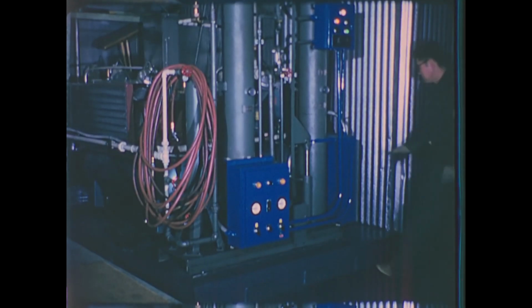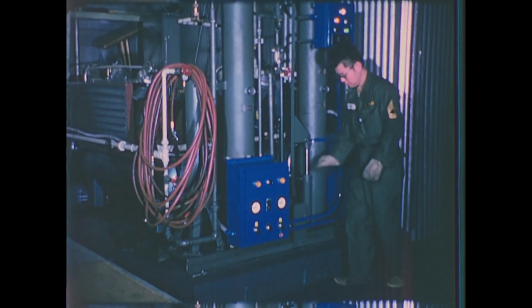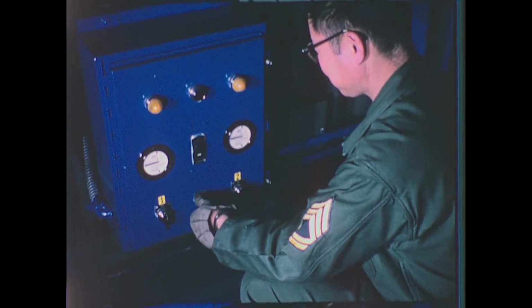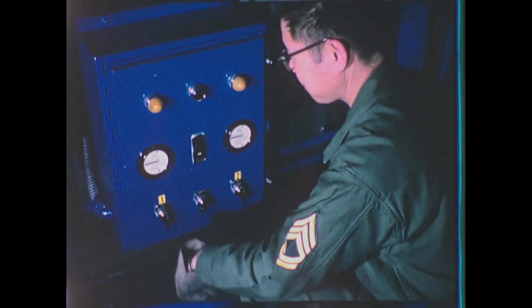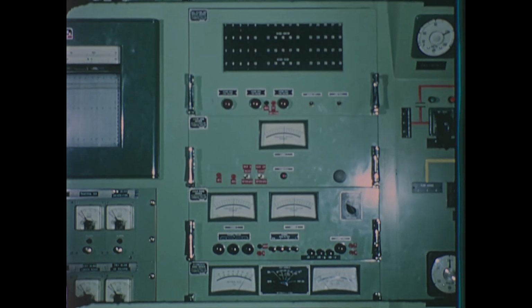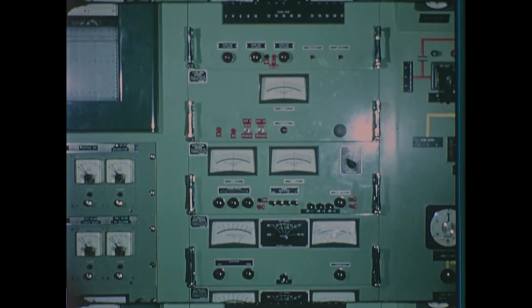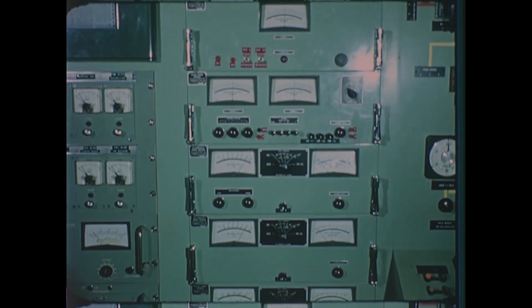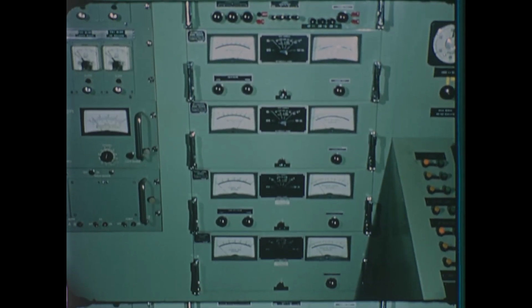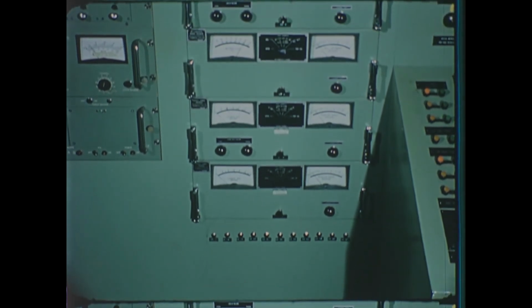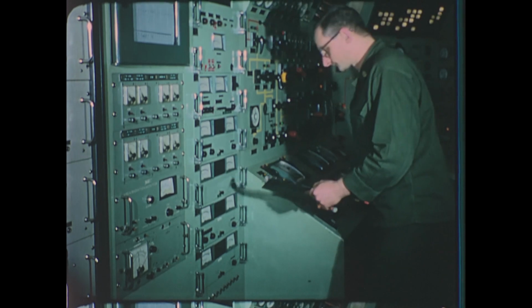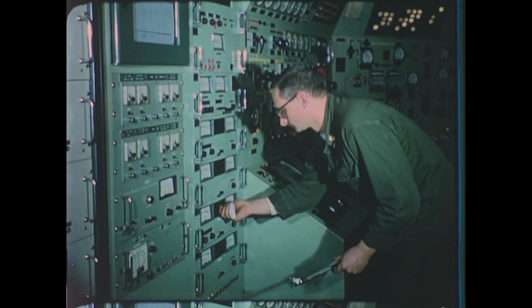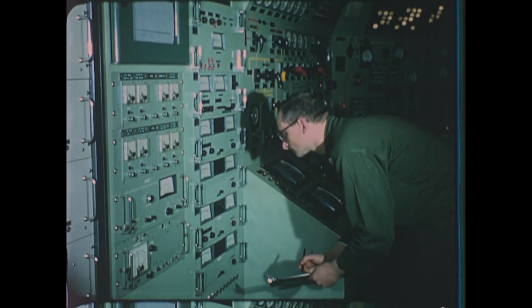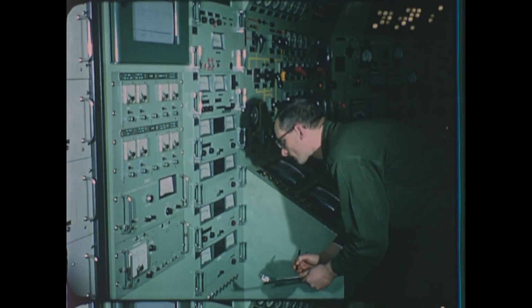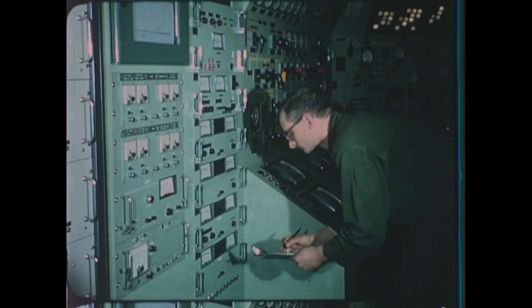An operational check of the air compressors that supply pressure to pneumatically operated valves and controllers. Pressure is maintained above 100 psig. The nuclear instrumentation panel, located at the console in the plant control room, is powered by the vital AC-DC electrical system. This is one of the areas checked during the pre-start procedure. The control room operator follows the console pre-startup checklist to ensure the proper operation of all controls and the status of all plant systems. His checklist, like the others, must be approved by the watch supervisor.